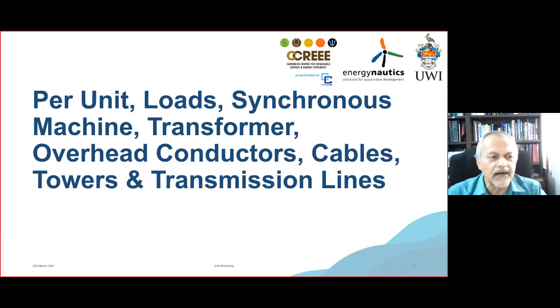Now, in a normal power system, we have several units to look at: synchronous machines, transformers, overhead conductors, cables, and transmission lines. We also know that all these systems are at different voltages. So in a power system, you start at the generating station, maybe at 12 kV or 13.5 kV, then step it up to transmission voltages, maybe in one or two steps, going from 33 to 132, back down to 66, then for distribution down to 12 kV or 13 kV, and finally to general utilization voltages of 220, 110, or 120.